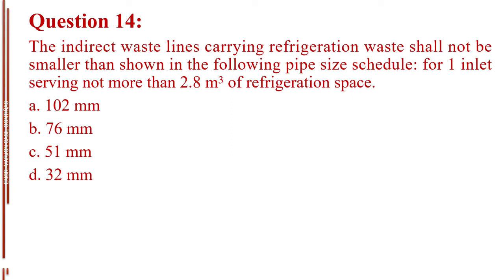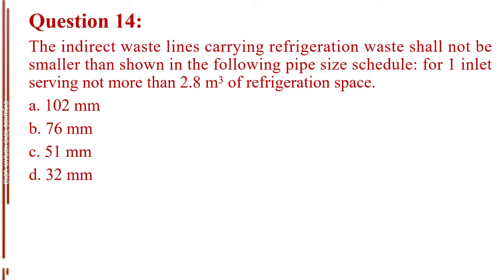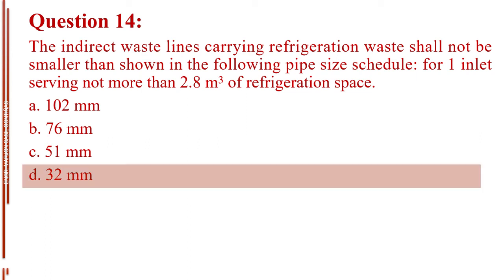Question number 14. The indirect waste lines carrying refrigeration waste shall not be smaller than shown in the following pipe size schedule, for one inlet serving not more than 2.8 cubic meters of refrigeration space. Letter A, 102 millimeters. Letter B, 76 millimeters. Letter C, 51 millimeters. Letter D, 32 millimeters. The answer is Letter D, 32 millimeters.